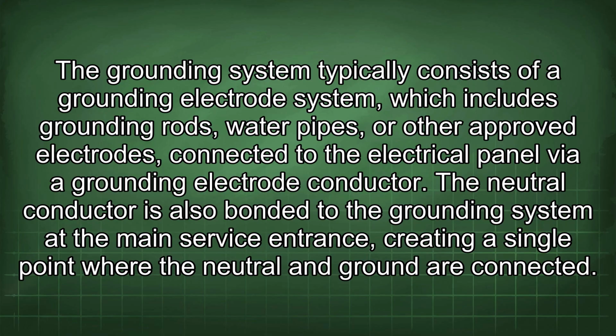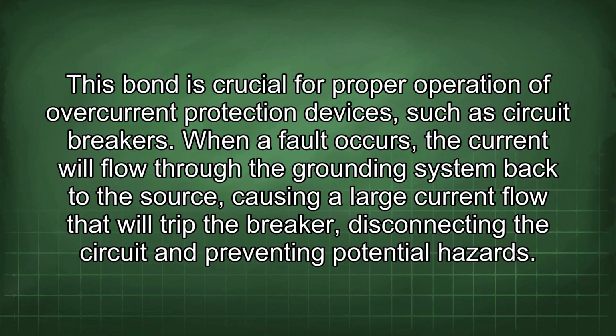The neutral conductor is also bonded to the grounding system at the main service entrance, creating a single point where the neutral and ground are connected. This bond is crucial for proper operation of overcurrent protection devices, such as circuit breakers. When a fault occurs, the current will flow through the grounding system back to the source, causing a large current flow that will trip the breaker, disconnecting the circuit and preventing potential hazards.